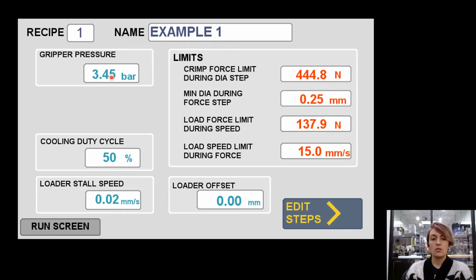Additionally, you can choose to increase or decrease the pressure to the clamshell gripper, which will change your clamping force on your catheter. You can also set the cooling duty cycle that's here. This is just a setting that dictates the percentage of time that the liquid nitrogen is flowing during your loading process if you're using liquid nitrogen cooling. Then you have the loader stall speed. This is essentially a lower speed limit for the auto pushrod loader. It tells the machine how slow you will allow the pusher to move during the loading process before it stalls out. Then lastly, this setting here is the loader offset. So this is the initial position of the loader at the beginning of a recipe.